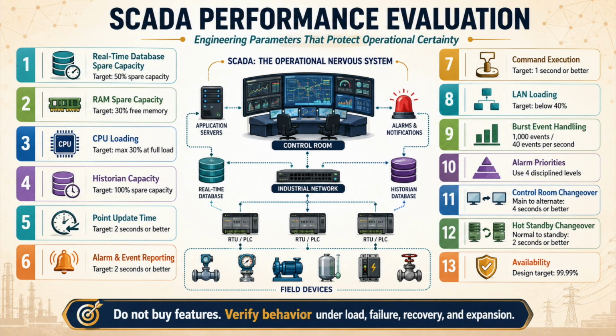A weak SCADA specification buys software features, while a strong SCADA specification buys verified behavior, and that behavior must survive expansion, communication failure, alarm storms, operator concurrency, server failure, control room transfer, historian backfill, network congestion, cybersecurity constraints, and the ordinary chaos of real industrial operation. For design engineers, instrumentation engineers, control system engineers, operations teams, and project managers, the mindset shift is direct. SCADA is not only screens, tags, alarms, and reports. SCADA is operational certainty, and operational certainty is engineered through performance parameters, architecture discipline, testing discipline, and acceptance discipline.